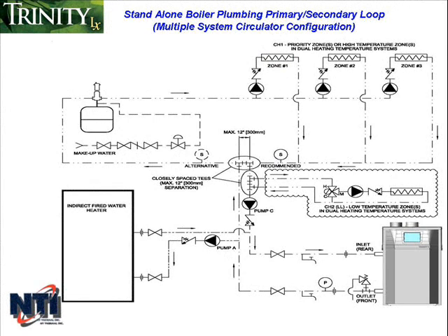This example shows the layout most often used in applications with zone circulators, and this configuration requires the installation of a check valve located at each circulator. Because in this layout there isn't a system circulator that comes on with every heating call the way there was in the previous example, you'll only use 2 of the 3 pump leads.